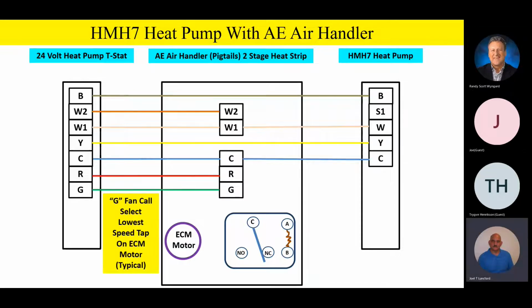G terminal is our fan call, and that's pretty standard in the industry. You're going to have a G wire, or green wire, typically from the heat pump thermostat over to the G terminal, or the green wire, on the air handler inside. Any questions or comments on the basic low voltage wiring so far before we start jumping into the relay and how we're going to hook up that standard ECM motor on an AE air handler? Any questions or comments so far?